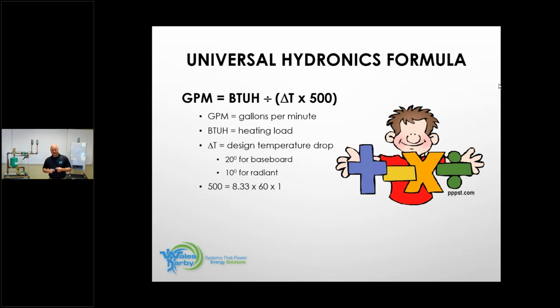treasure this piece. What is this telling me? GPM. We just talked about that. That's gallons per minute. Equals BTUH. That's our load, right? That could be our boiler capacity. That could be a heating zone capacity. That could be anything that needs BTU. Okay? We don't have to use this formula in only one type of application where all I care about is the size of this boiler. That's not necessarily the only. That's definitely not the only use of this formula.